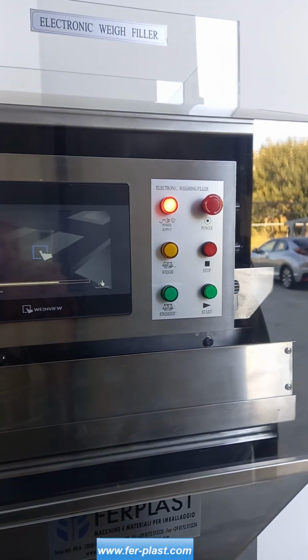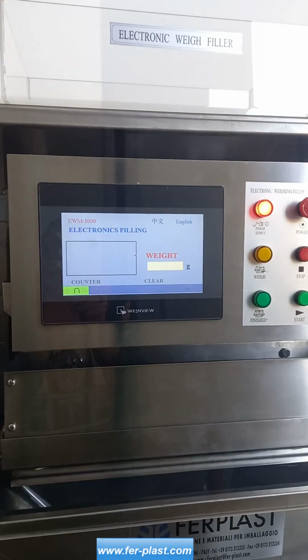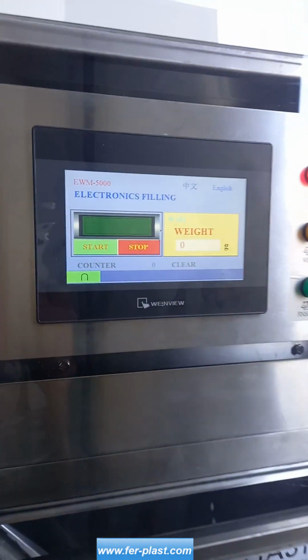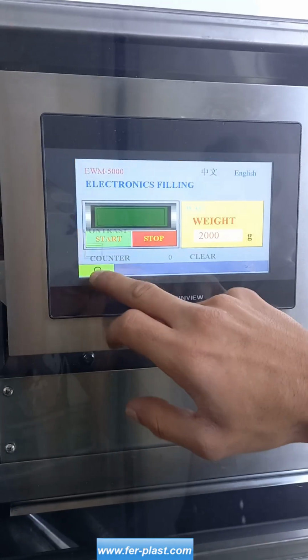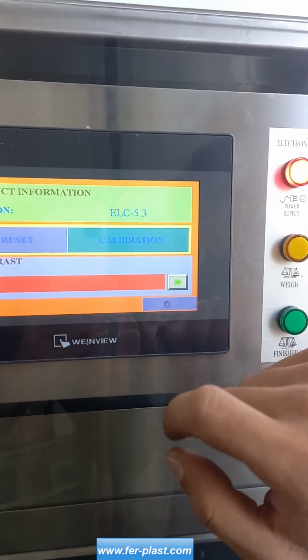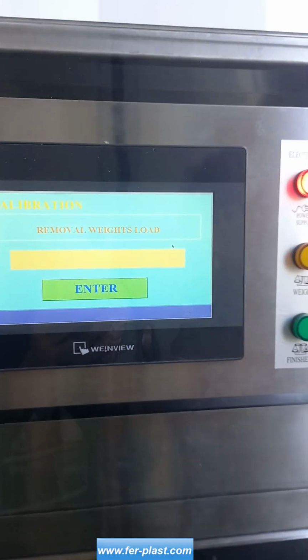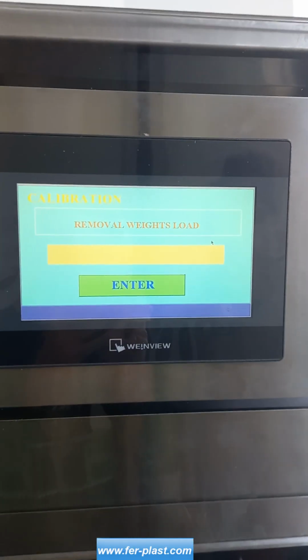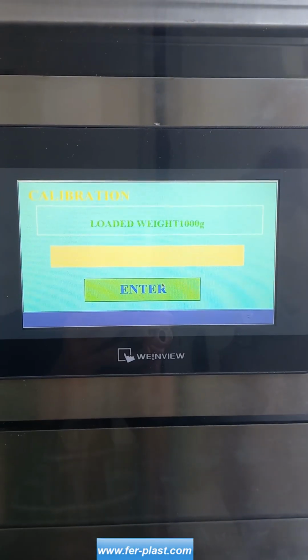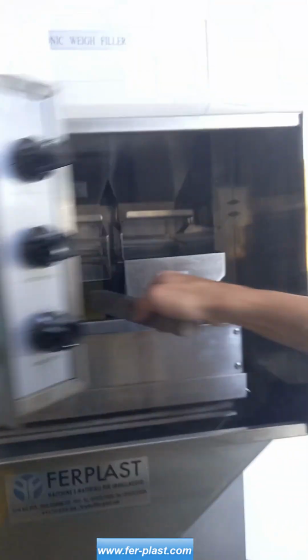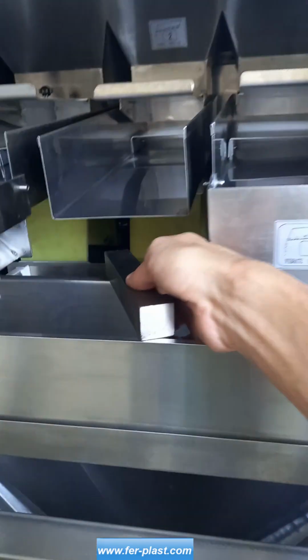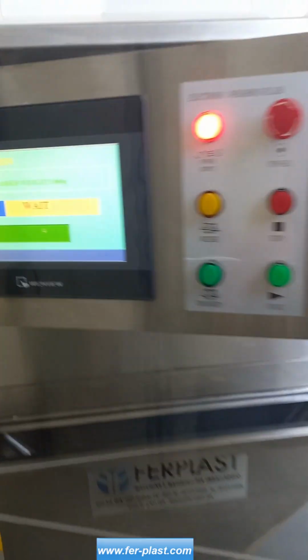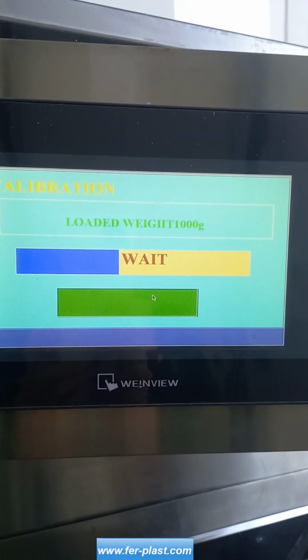Next, we turn on the doser and perform the calibration of the load cell. To do this, we enter the calibration menu and press enter. At this point, we place the 1000 G weight, supplied with the machine, on the load cell, and wait for the calibration procedure to be completed.